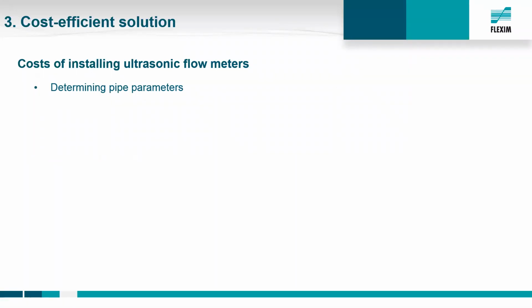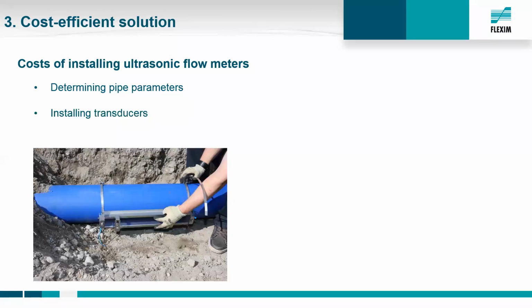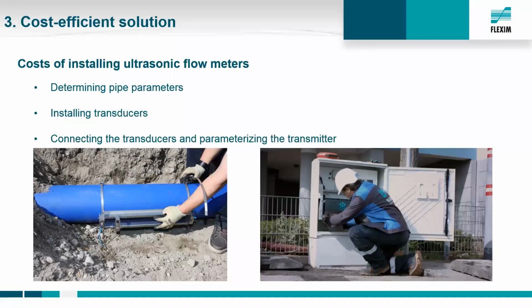For sure, the ultrasonic flow meter needs work as well. Once the pipe is accessible, we have to determine the pipe parameters, especially circumference, pipe material and wall thickness. Then we have to install the transducers properly with the proper transducer distance, connect the transducers to the transmitter, and the transmitter to the junction box, and start the measurement. I just focused here on the differences. Some of you may say we also have to consider the excavation, and yes, I agree, sure, we also have to consider the excavation and other works, but these are the same for both techniques, so I'm just focusing on the differences. And then it comes to mind that the installation of a non-invasive flow meter is definitely less effort and lower in cost than an inline meter.